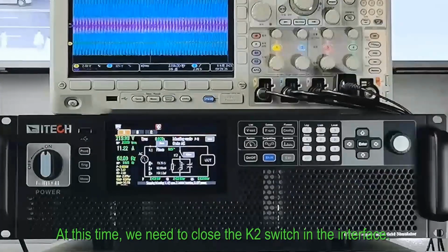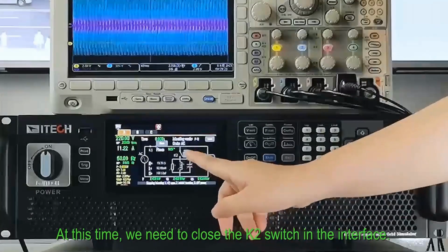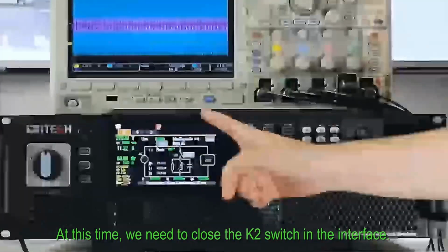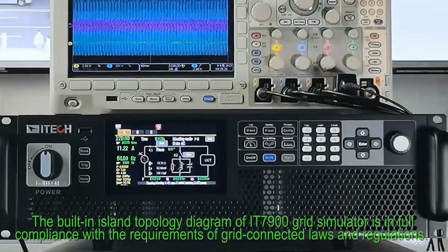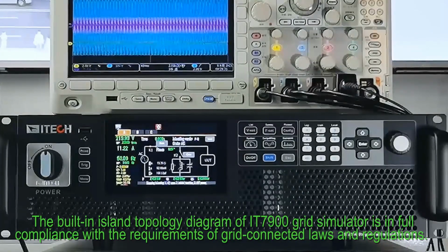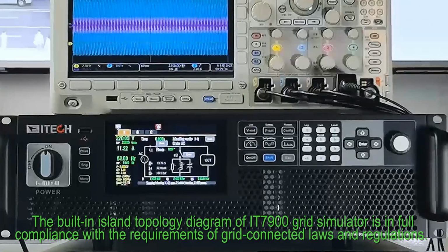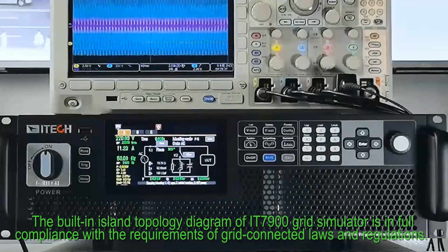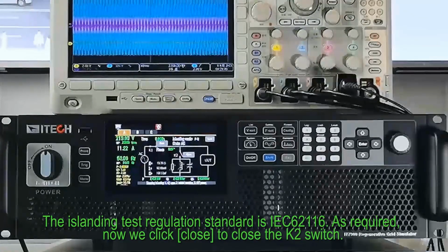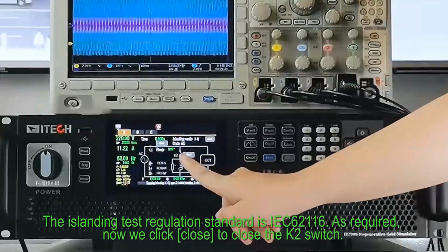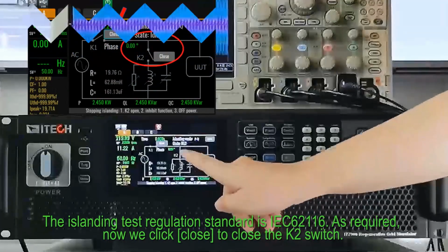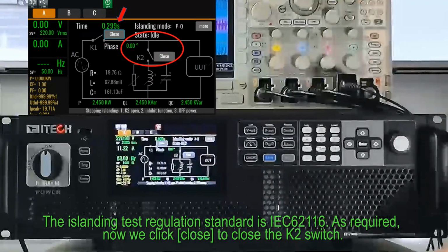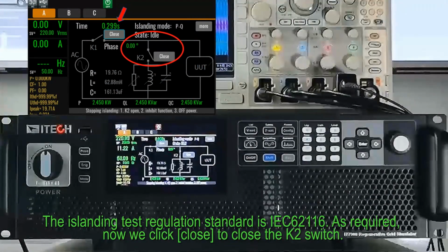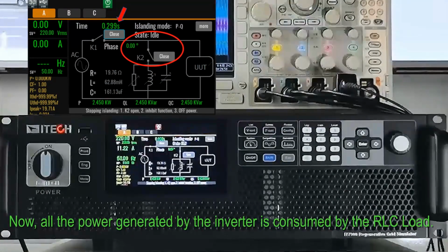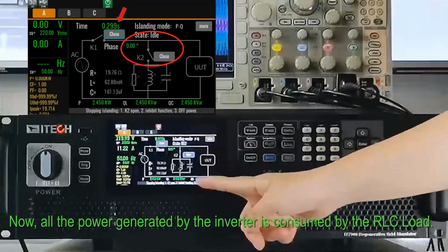At this time, we need to close the K2 switch in the interface. The built-in islanding topology diagram of IT7900 grid simulator is in full compliance with the requirements of grid-connected laws and regulations. The islanding test regulation standard is IEC62116. As required, now we click Close to close the K2 switch. Now, all the power generated by the inverter is consumed by the RLC load.